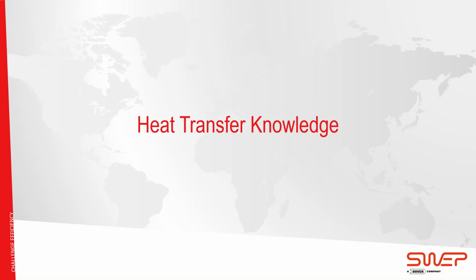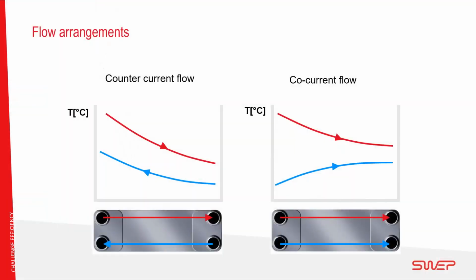Pleasure. So I'm just going to cover a bit more of the technical details concerning a brazed plate, starting with some heat transfer knowledge. It's first worth mentioning that heat transfer efficiency can be affected by the flow arrangement. There's two possible arrangements that we typically see. We have countercurrent on the left, which is when the two fluids enter the heat exchanger at opposite ends, and hence the flow is in the opposite direction.